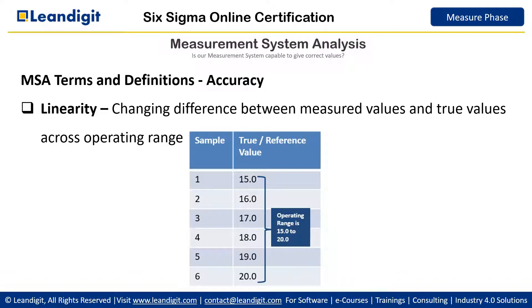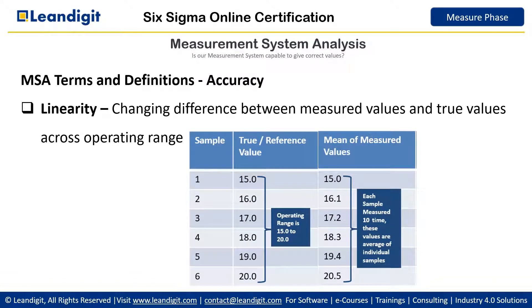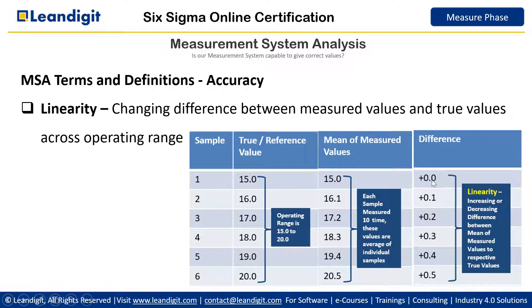Now let us take the same samples but with another instrument. When we measured the sample with true size 15 ten times, the average came out exactly 15. But when we measured sample 2, which has actual size 16, we got 16.1. When we measured 17 ten times and took the average, it came to 17.2. We see this bias is increasing as the value of the sample increases. When there is an increasing or decreasing difference between the measured value and the true value across the operating range, we call it linearity.